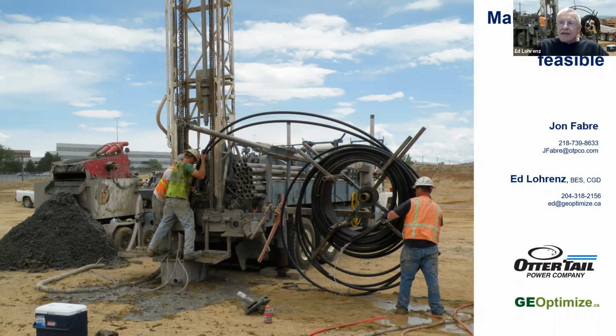Yeah, in some cases. I don't know the math behind it in detail, but from what I've seen in projects, because the ground heat exchanger acts as an energy storage medium more than an energy source, I believe some of the impact comes from dumping the heat into the ground, and where it's dissipated into the ground, you can actually take advantage of the heat that you're dumping into the ground in the summertime and pull it out more easily if the boreholes are spaced more closely together.